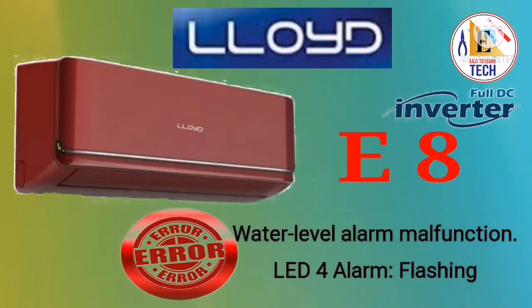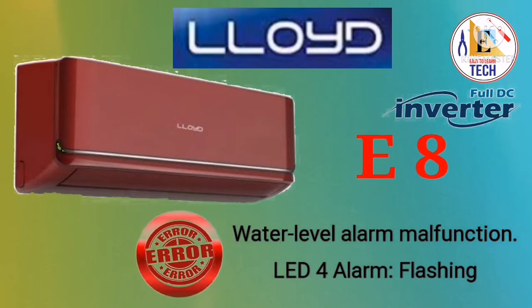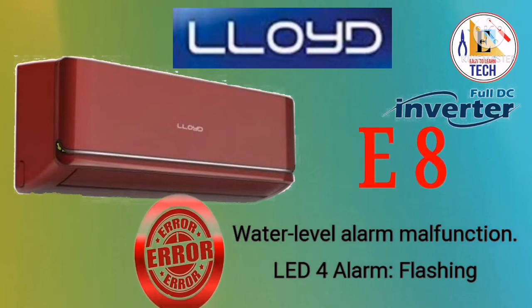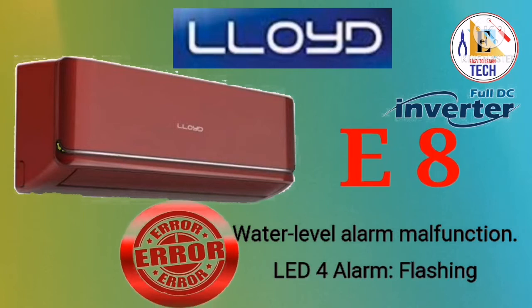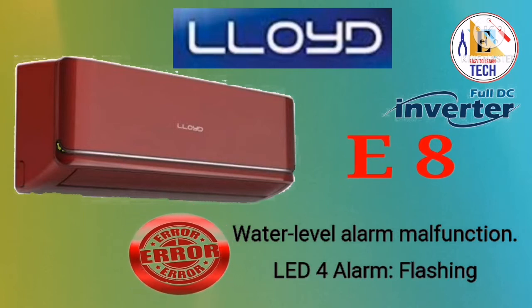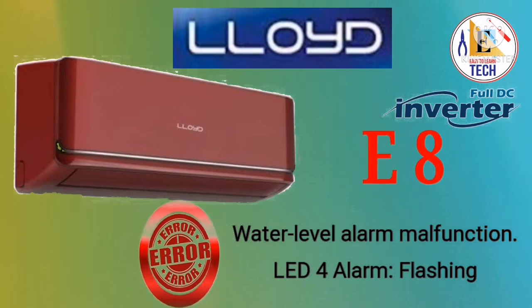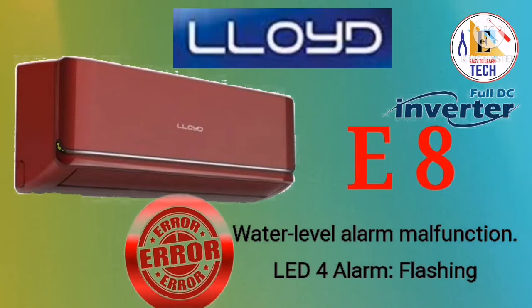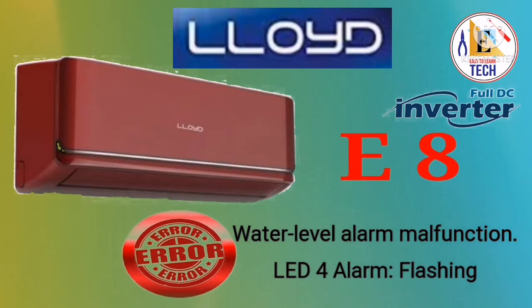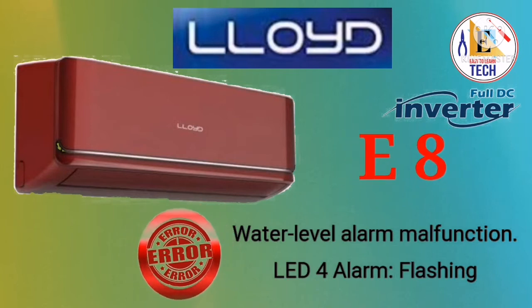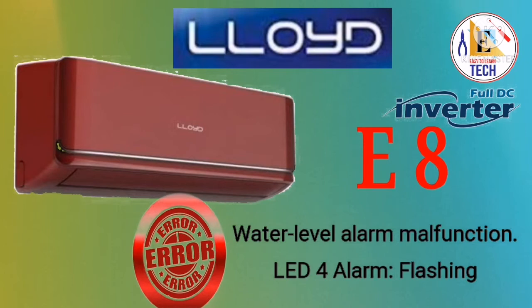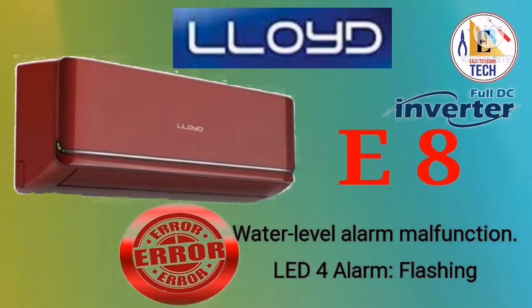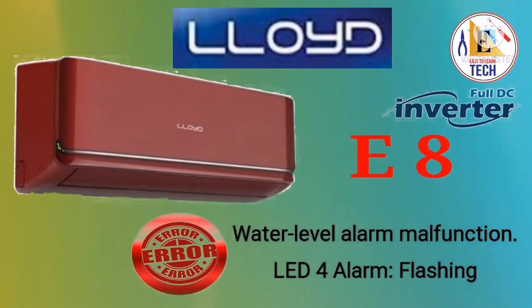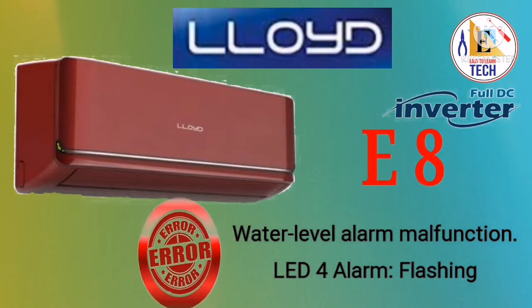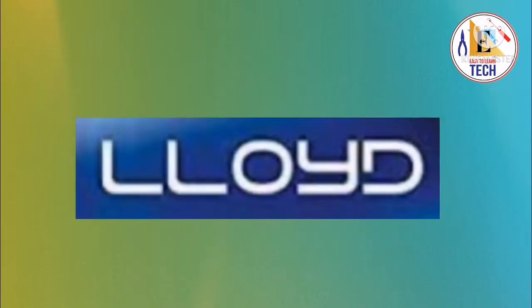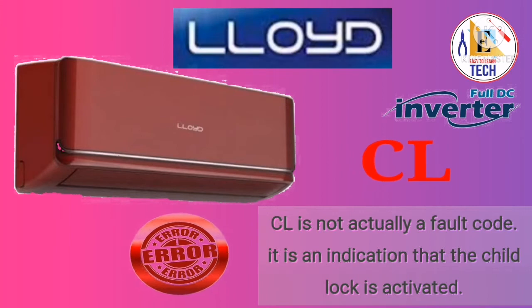When you see E8 in your display, it is for the cassette Lloyd air conditioning error code, because E8 means water level alarm malfunctioning. When the motor in the indoor unit of our cassette type is not working and the water level increases, at that time it shows the error E8 or LED4 alarm flashing. At that time you have to do the servicing of your indoor unit and clean the pump of your cassette type air conditioning, and you will get the solution for the error E8. The water will drain properly, there will be no leakage and no water level alarm malfunctioning. Do the servicing and you will get the solution for the error E8. Let's see the next error code.